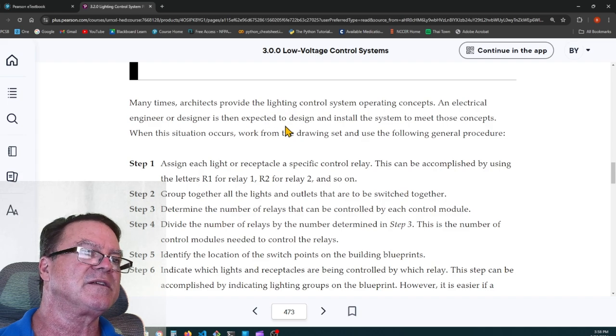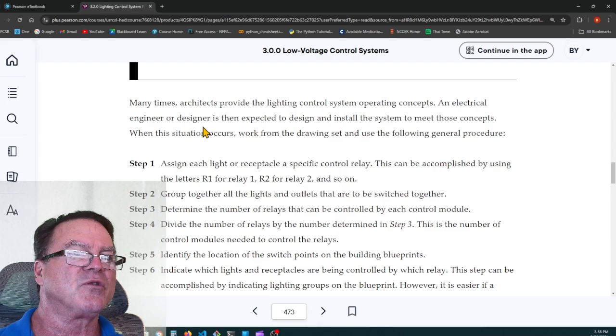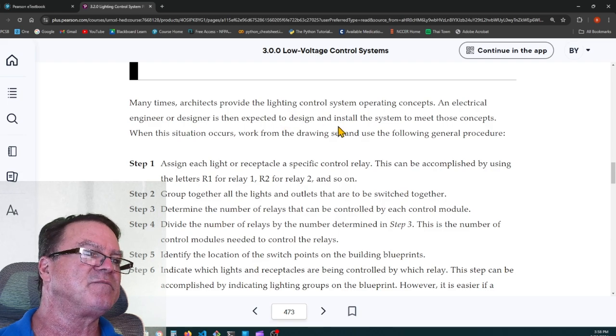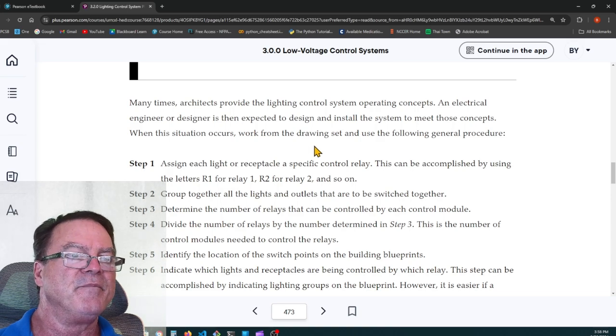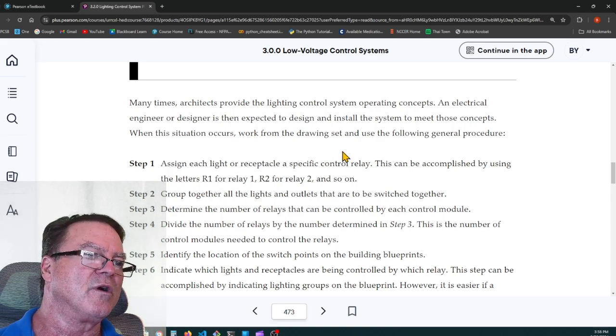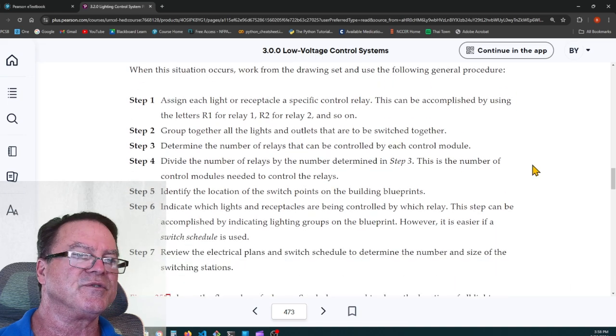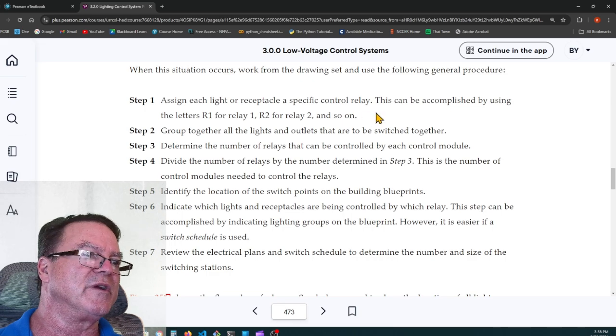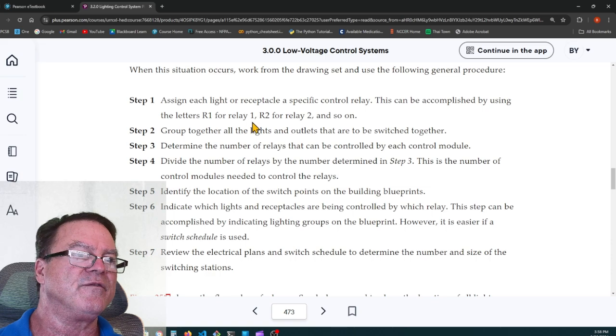Many times, architects provide the lighting control system operating concepts. An electrical engineer or designer is then expected to design and install the system to meet those concepts. When the situation occurs, work from the drawings set and use the following general procedures. Assign each light or receptacle a specific control relay. This can be accomplished by using the letters R1 for relay 1, R2 for relay 2, and so forth.